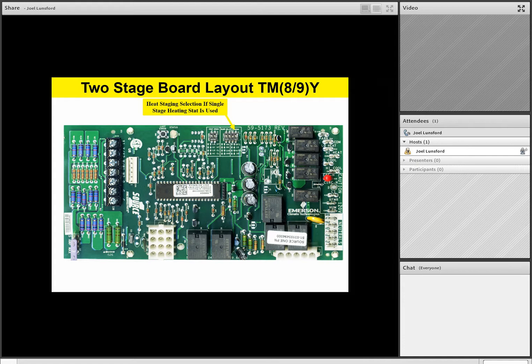these dip switches. You'll notice that if both of those dip switches are in the up position, it's off and we've disabled that function. If the dip switches are both down, what will happen is if you get a call for heat, 20 minutes later it will go into second stage to finish the call. And then there's also another function called 10. That's 10 minutes, so it's a time function. If you have it in the 10 position, what will happen is if you get a call for heat from the thermostat, if the thermostat hasn't satisfied in 10 minutes, it'll go ahead and put the furnace into second stage.